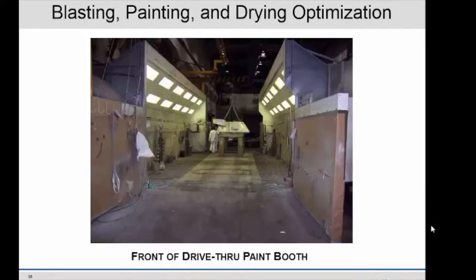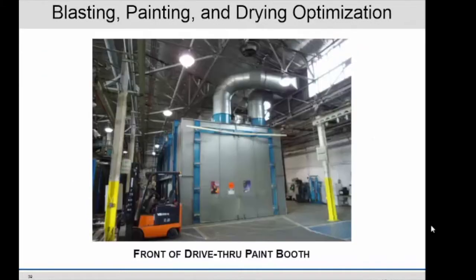Big painting booths. You'll see these painting booths. This is Rock Island, where they're just open to the space. So that whole big building there, you see the lights up there. This whole big building has this high ventilation rate. So it's better to go to more portable units like this. So if you put in a more portable unit, all you have to ventilate is that box, and you don't have to ventilate that whole building at a real high ventilation rate.